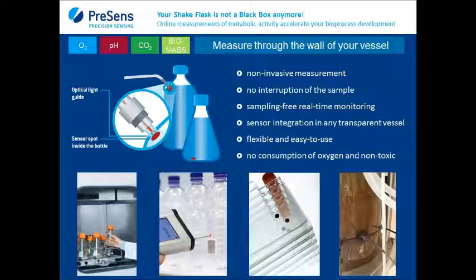The basic principle of these optical sensors is a small patch of fluorescent membrane that is integrated into your vessel. It is glued to the wall of your vessel, on the inside of your vessel, and is read out from the outside through the wall. So all you need is optical contact to your probe. You only need to be able to shine light through the wall of your vessel. So it will not work in a black vessel or in a stainless steel vessel, but for all disposables, plastics, glass, it will work. The disposable or the wall can even be amber colored, or it can be turbid, doesn't matter. Also, the solutions that you measure, they can be colored. They even can have background fluorescence. Our probes are optically insulated against those influences.